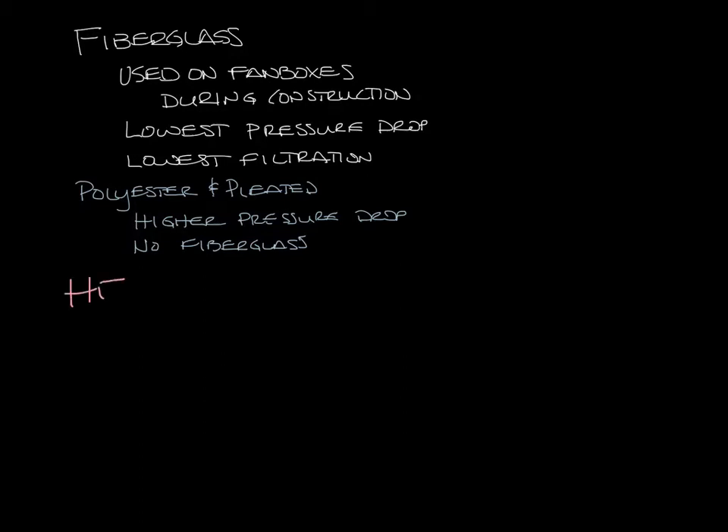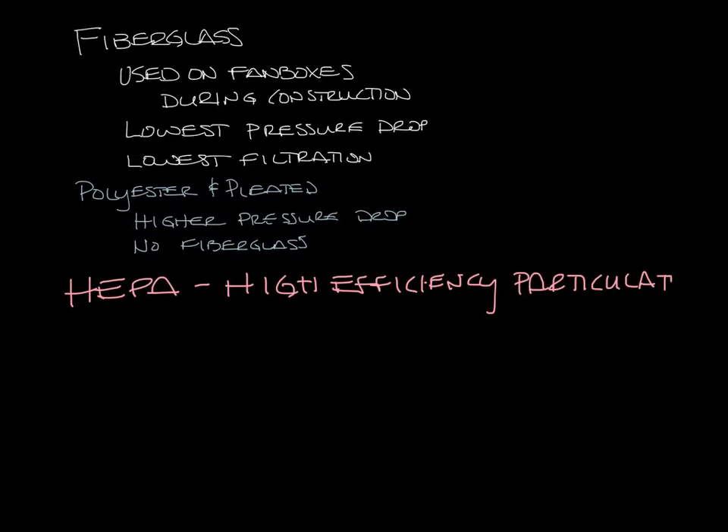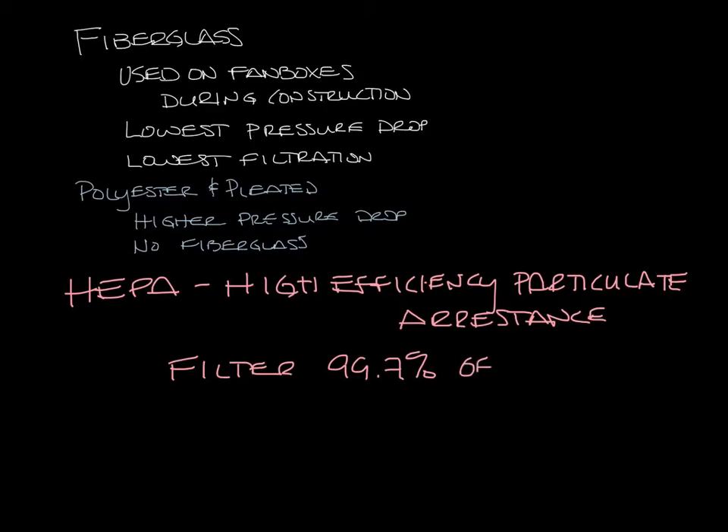Next you have HEPA filters. HEPA stands for high efficiency particulate arrestance, or you'll hear high efficiency particulate air filter, which is easier to say. They filter at a much finer scale and filter 99.97% of all particles 0.3 microns or larger.